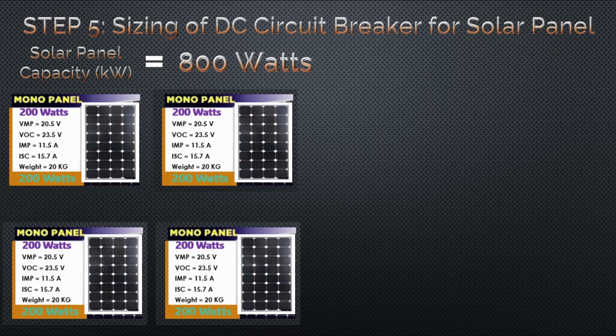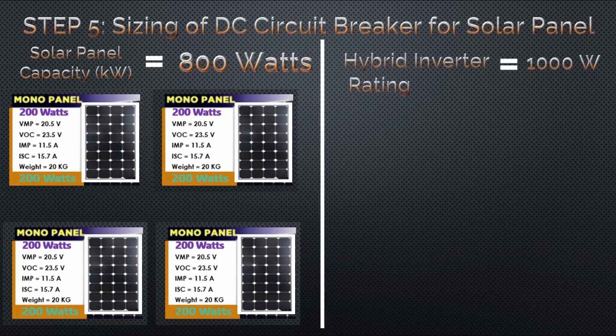We already discussed earlier in this video how to size the inverter, and the rating we get is 1000 watts. So the next thing to do is to look for the rating of a hybrid inverter available in the market with 1000 watts rating, and then look for the specification of the DC voltage range, because it will be your reference on what connection you will make for the solar panels. For example, the nameplate of the hybrid inverter has an operating voltage range of 30 to 150 volts DC.